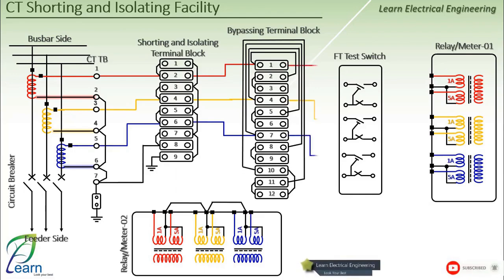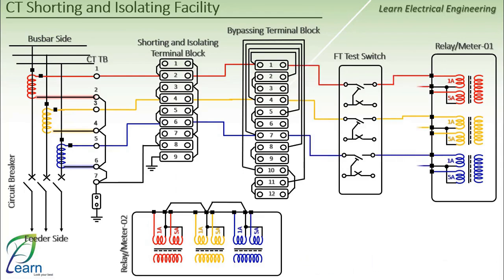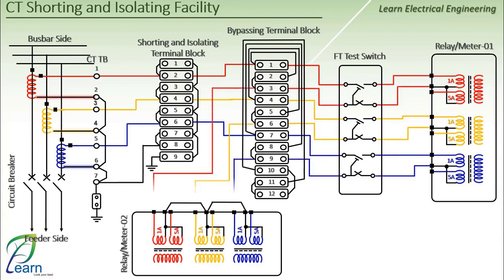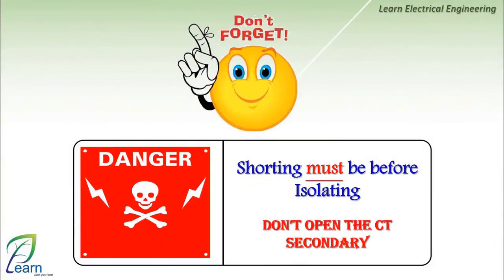Then I exit to the test switch and from there to the first device, and then return again to the test switch. Then the bypassing TB, from which I will go to the second device, and finally return with the neutral wire. Now we will start the practical session together, but the most important thing is not to forget our rule. Shorting must be done before isolating.